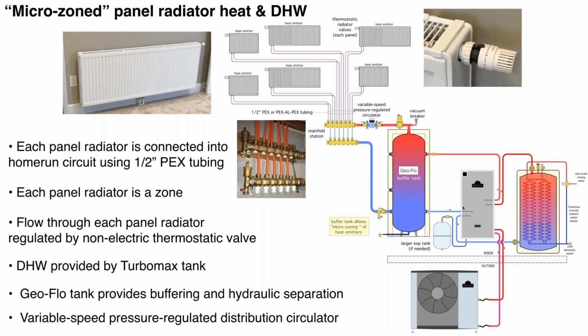And as far as the balance of the system, we've got our standard Advantage heat pump setup, except for one substitution. What I've done is I've removed the hydraulic separator and I've installed the GeoFlow buffer tank. This is a polypropylene pressure vessel with fiberglass as a reinforcing shell, very well insulated. And what it does is it adds thermal mass to the system. One of these panel radiators, if it was turned on, could have a very low demand for heat, maybe 1,000 or 1,500 BTUs per hour. Well, even though the Advantage heat pump is a modulating unit, it doesn't modulate that low.